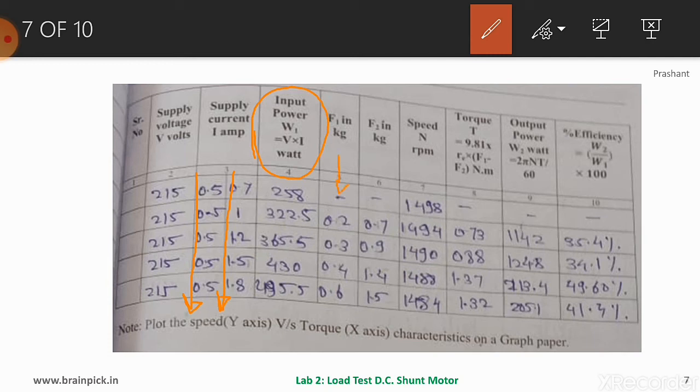The input power column is calculated by multiplying voltage and total current. F1 and F2 are in kilograms — both can be varied, or only one may vary while the other remains constant. Speed in rpm is measured by the tachometer. Torque is calculated using 9.81 × r × (F1 − F2) in Newton-meters. Output power is calculated as 2πNT/60, and efficiency as output power divided by input power. The first reading at no-load shows no spring balance readings, and speed is 1488 rpm, near the rated 1500 rpm.